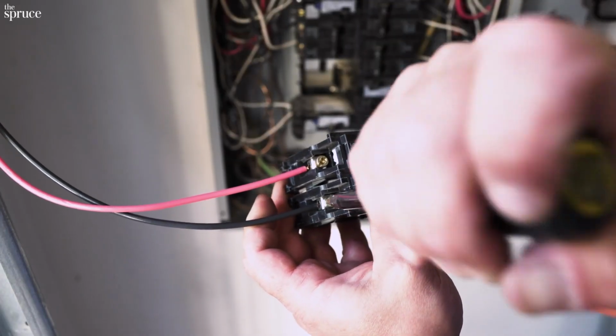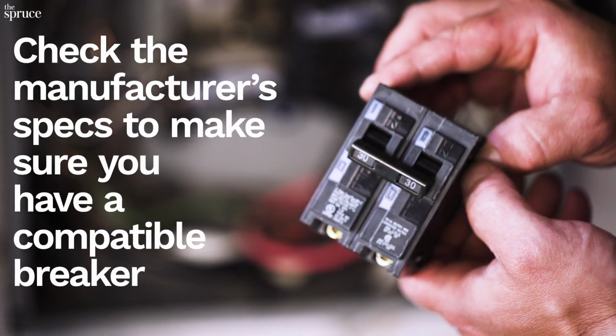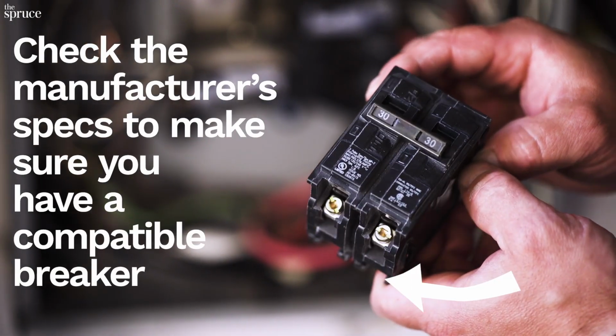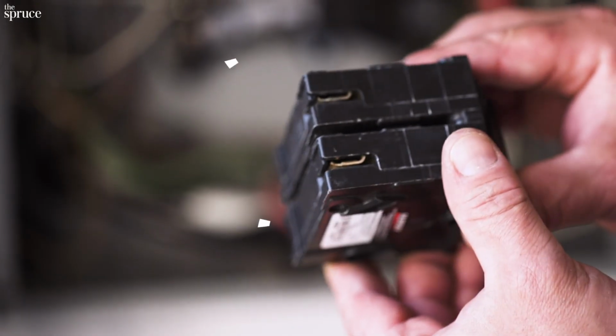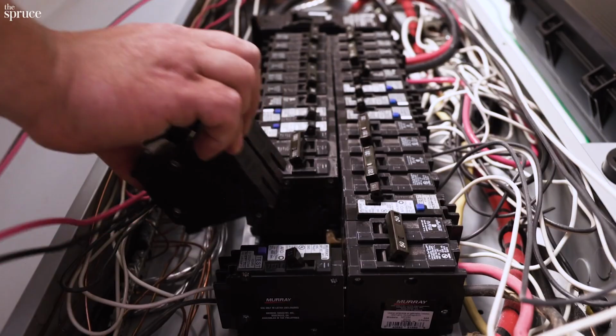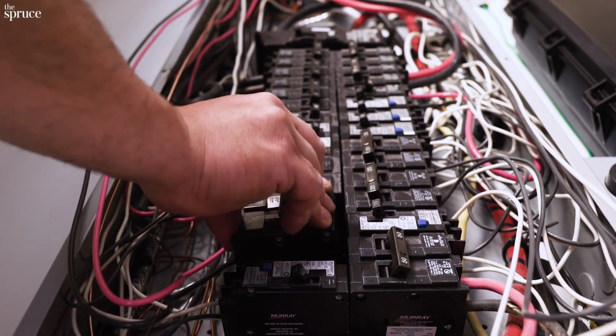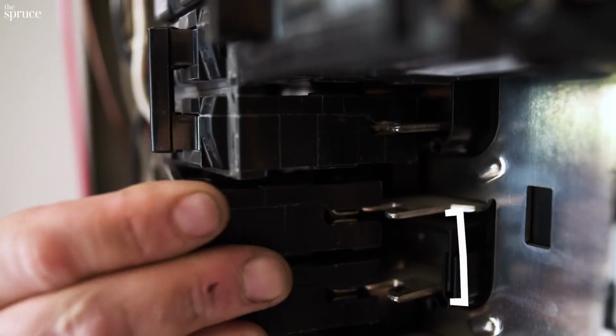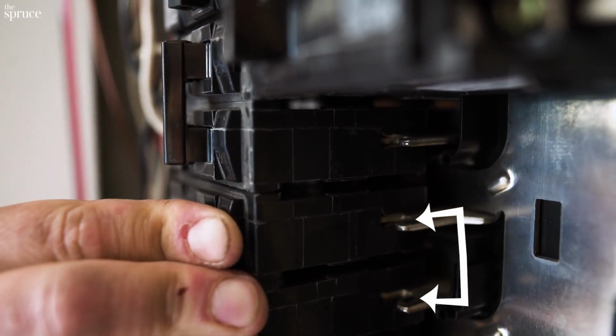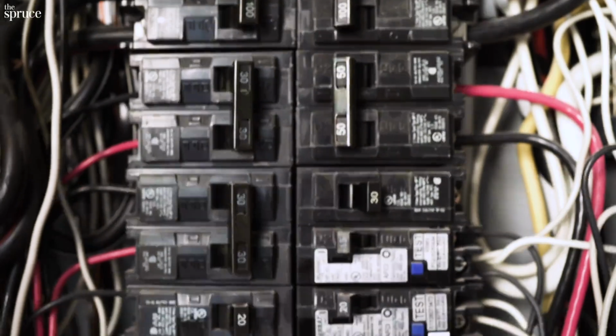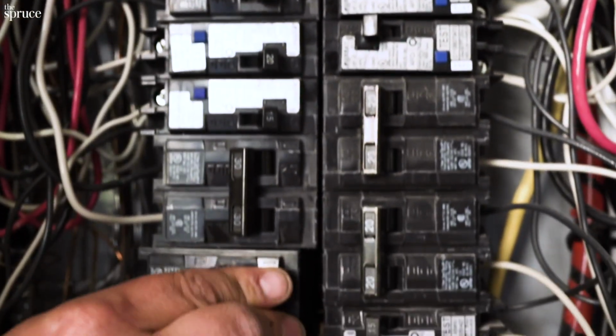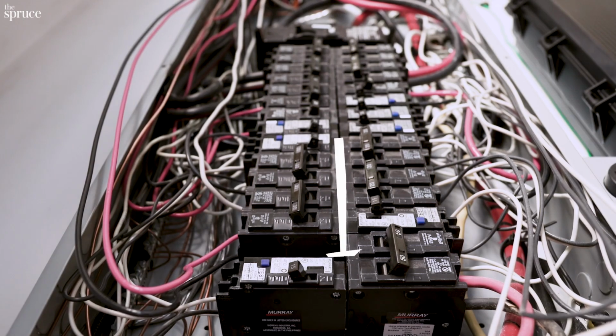Always make sure your breaker is compatible with your panel. Most breakers have tabs on the outer bottom corner and slots on the inner corner. You hook the tabs into the outside of the bus bar. Then you pivot the breaker towards the center, and the slots fit onto these knife blades on the bus bar. Push the breaker down and it snaps right into place. Make sure it's flush with all the other breakers and not sticking out.